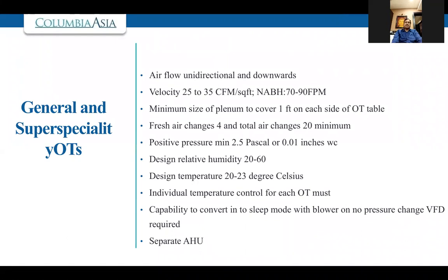So velocity also we have changed in the revised guidelines. If you can see, 25 to 35 CFM per square feet. Repeat, per square feet. Earlier guidelines were 70 to 90 feet per minute, which is almost similar to what 25 to 35 CFM per square feet comes to, if it is through the plenum. Minimum size of the plenum should cover the operation table, 1 feet on each side. This has been mentioned specifically in our guidelines also.